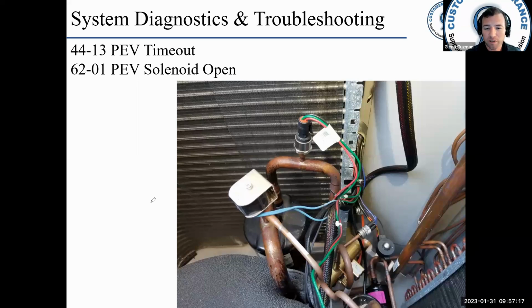I would caution you against jumping to that conclusion with this fault, because the couple times I have seen it, it's been related to a transducer. What I've found with troubleshooting this unit is these fault codes are very descriptive and they do help you narrow it down, but you want to look at everything as a whole. You don't want to say, okay, I got 4413, the manual says change the PEV, that's what I'm going to do. You want to stay away from that train of thought. You want to look and see what fault codes you have in addition to 4413, and whether they correlate to each other at all.